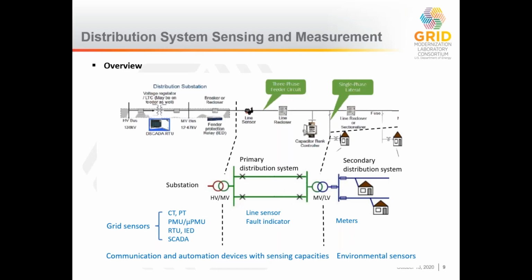In homes, aside from the smart meter network, we also have things like environmental sensors, temperature sensors, and irradiance sensors, which help us forecast better and control different variables in the network. For example, when you have a 110-degree day in Livermore, we sometimes lose one of the transformers. Being able to focus on that, knowing what the temperature is and what you're predicting, and having enough data to validate that, is important for managing your load further downstream and making sure we can keep going when we need to. So next.